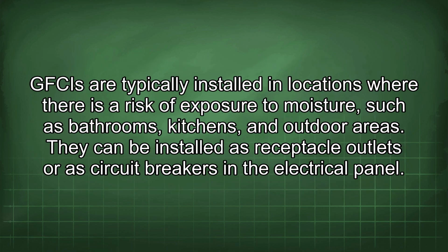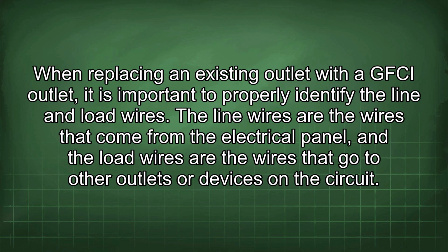GFCIs are typically installed in locations where there is a risk of exposure to moisture, such as bathrooms, kitchens, and outdoor areas. They can be installed as receptacle outlets or as circuit breakers in the electrical panel. When replacing an existing outlet with a GFCI outlet, it is important to properly identify the line and load wires. The line wires are the wires that come from the electrical panel, and the load wires are the wires that go to other outlets or devices in the circuit.